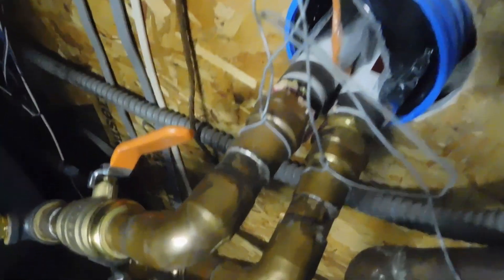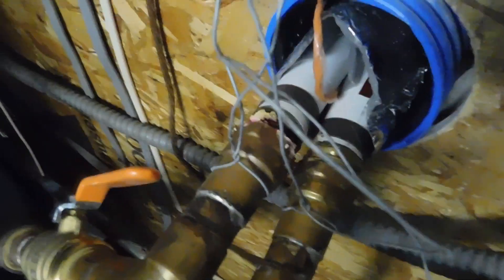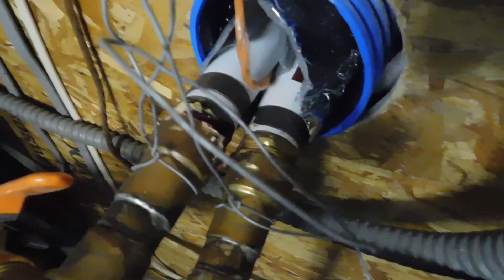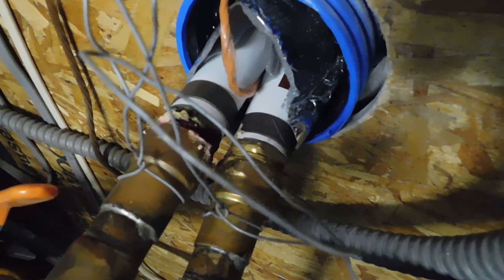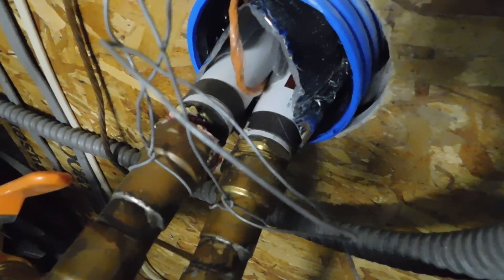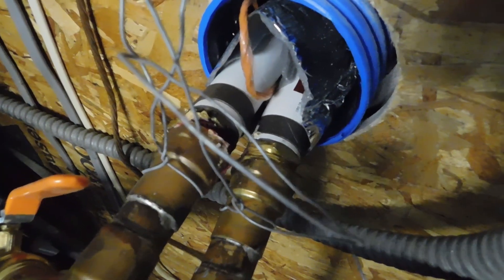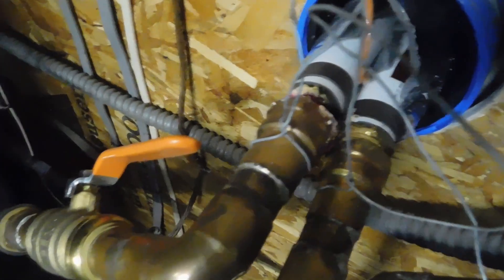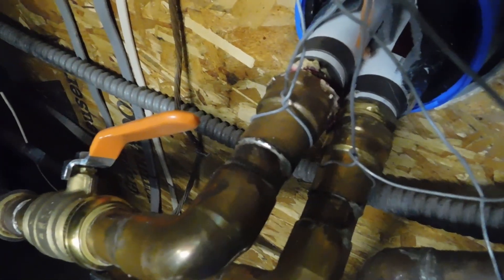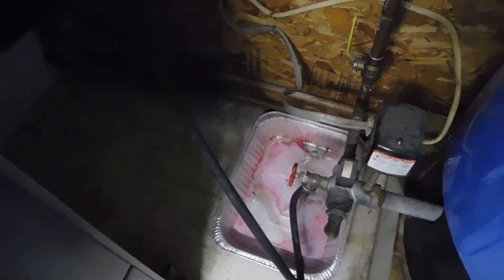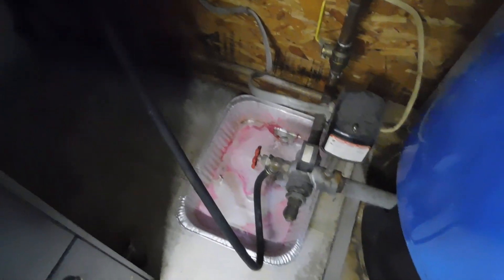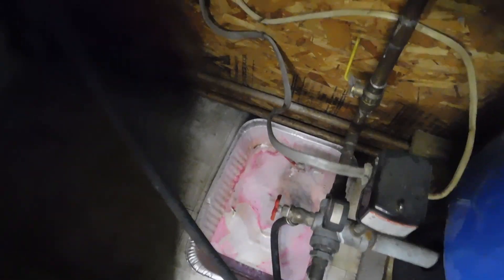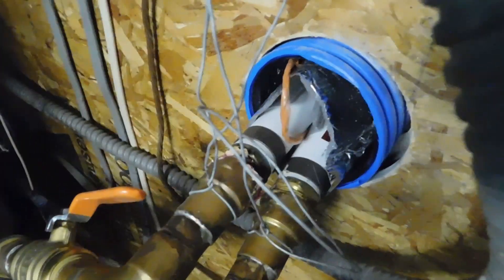It's tedious, it takes a while. You know, I'm gonna have to tighten these up, put some new pipe dope on them. I fixed one already, it started leaking as soon as I started filling the system. So I was able to stop, blow out the lines, redo that fitting and it worked. And then the second one here, the return line, didn't start leaking until a month later, which is what the pan is for down here. And it was just like a couple drips an hour, just enough to be irritating but nothing that overflowed. So I'll fix that this summer.